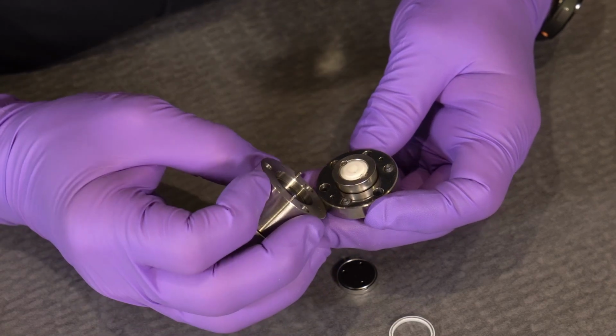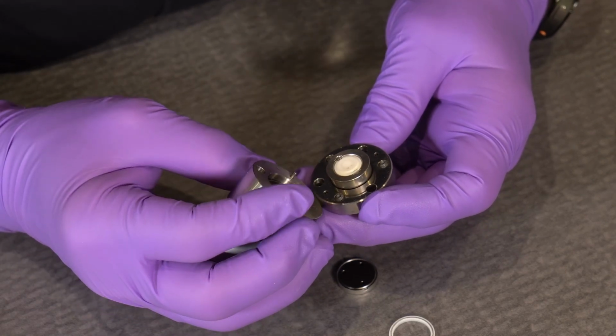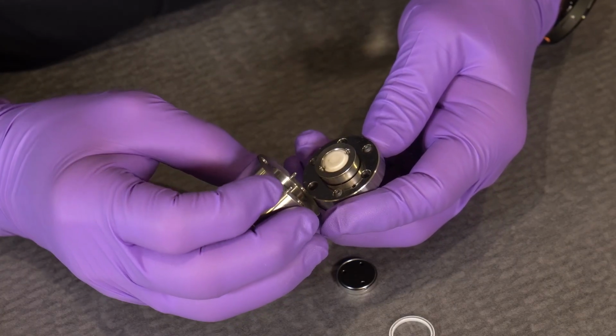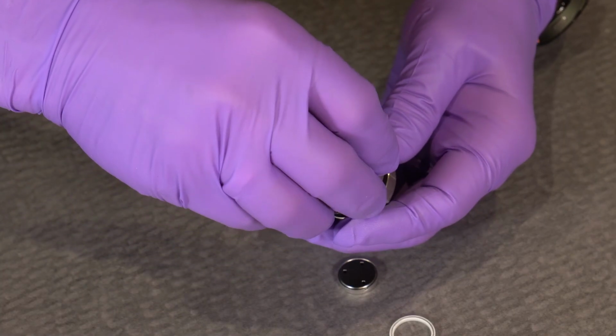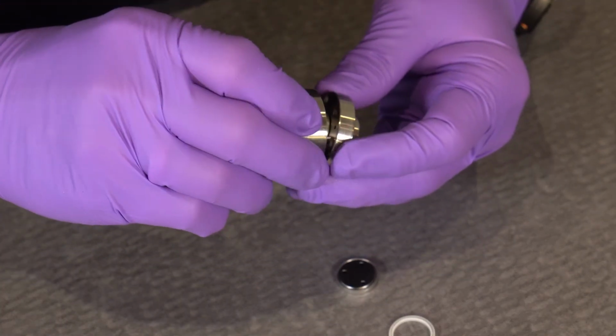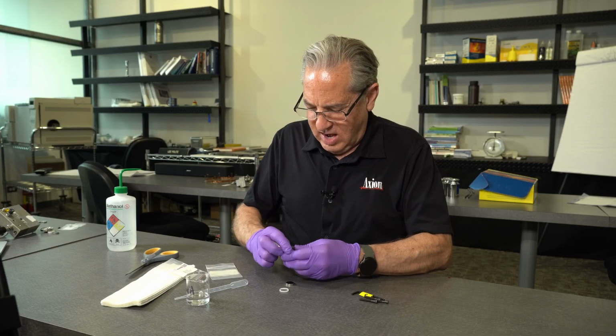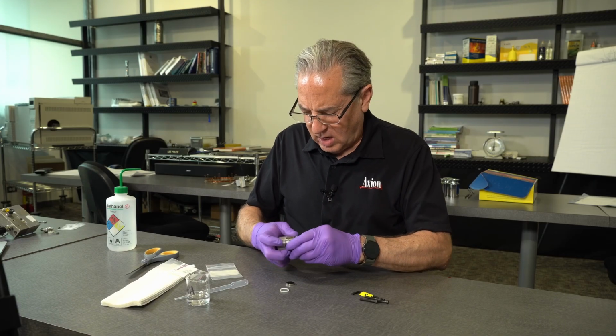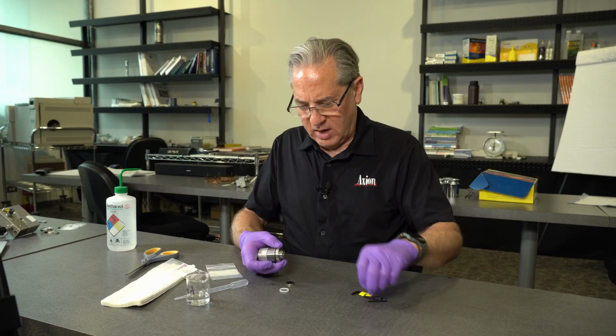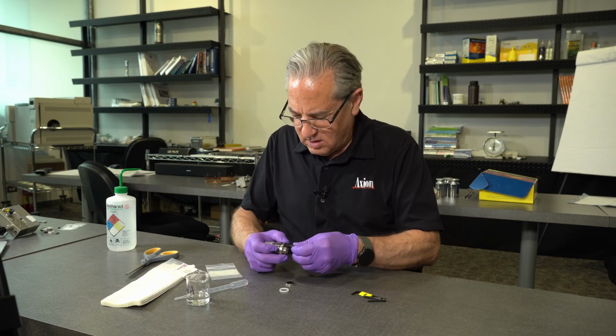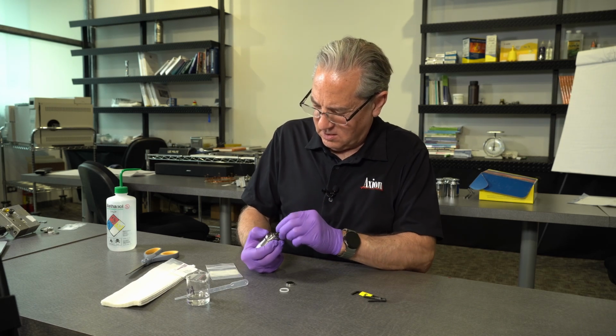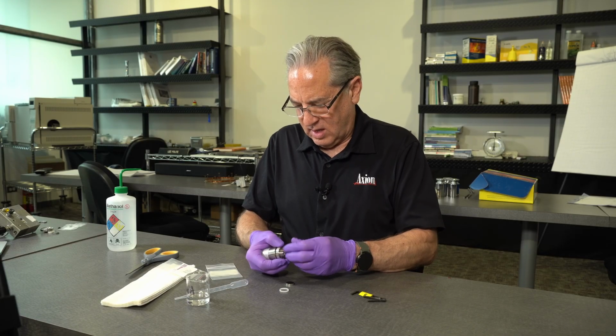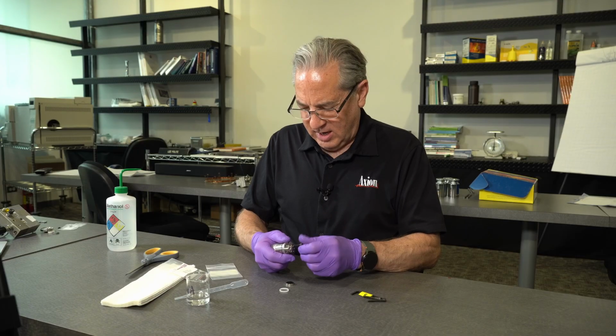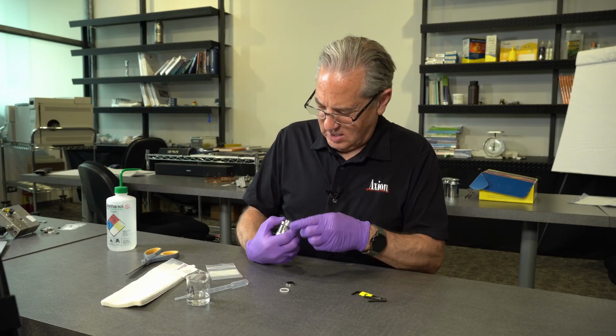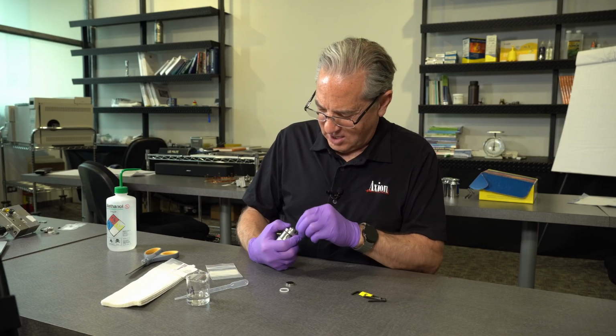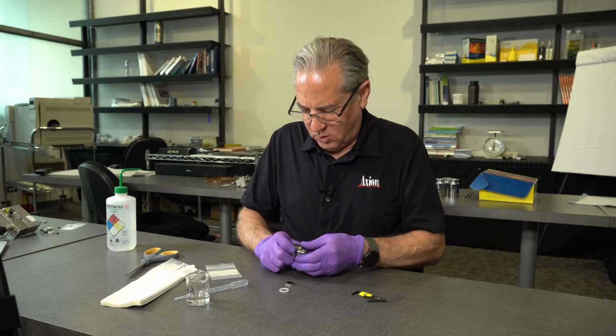So the 3 holes have to match where the screws are going to come in, and then these 2 pegs have to match as well. So I think if we do it like this, we're going to see these 2 pegs match up, and when I put it back together, we will set them in like this. And then when you start to put the valve back together, remember this is going to be on the instrument itself. We go back to our 3 screws, and we put them in there. Once they go in, it'll make your life a little easier, because it'll help you line up the rest of the valve. So again, it's a little easier when it's on the instrument itself, because you don't have to hold this extra piece. It's actually being held in there for you, and that will help you line it up.